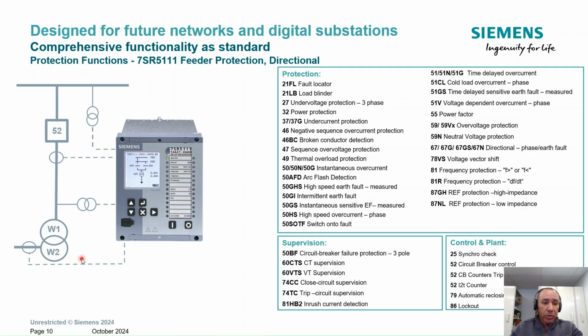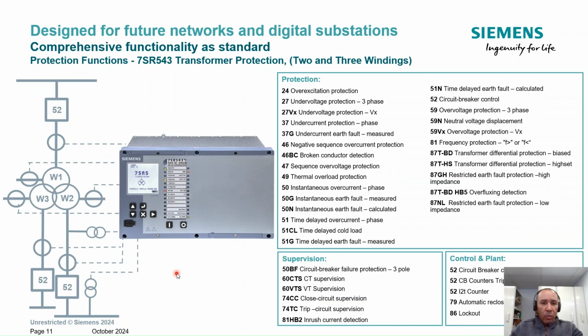This particular model cannot protect, but it brings a fifth input for the neutral, so you can perform any type of overcurrent for the neutral. Okay, we go with the second application. That's the transformer relay, 7SR543 for 3 windings and 542 for 2 windings.